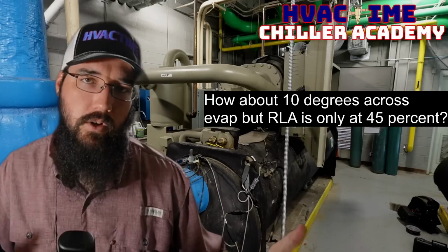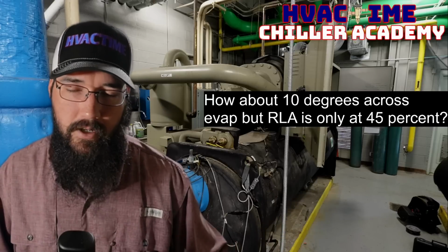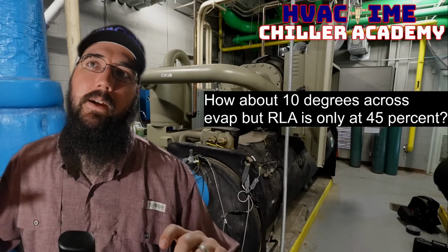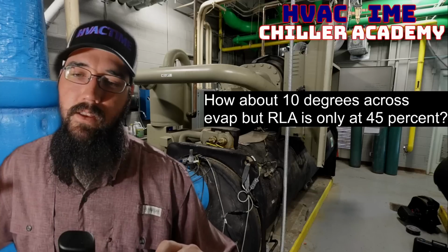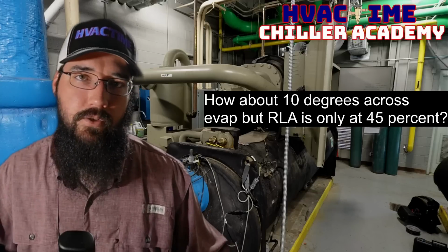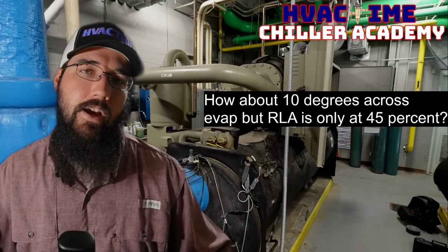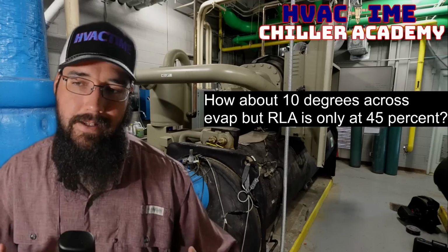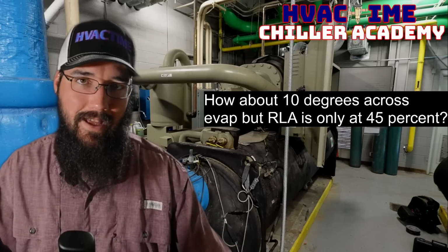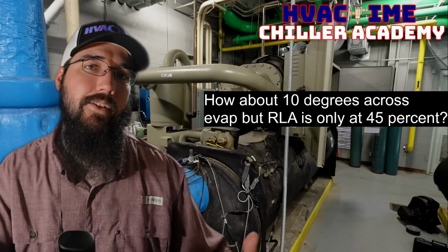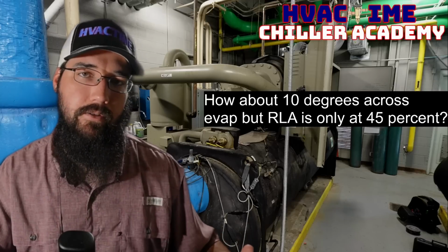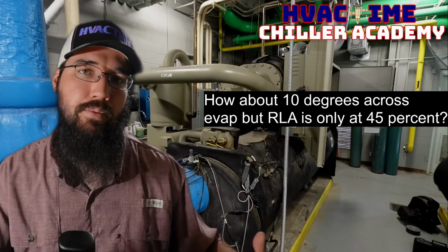Now, there's oil ramifications and stuff if we're not careful with this, but ultimately, if we get our condenser pressure down and our head pressure down, then again, we have to compress less. It's not as hard to get it from the evaporator to the condenser at the proper saturations.